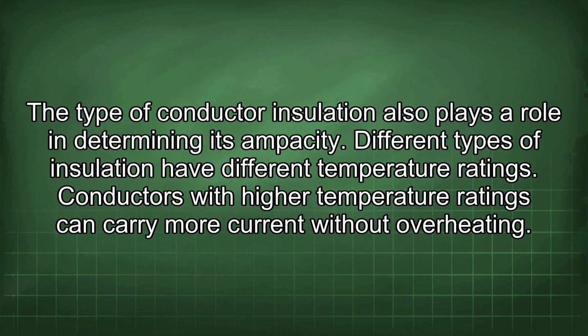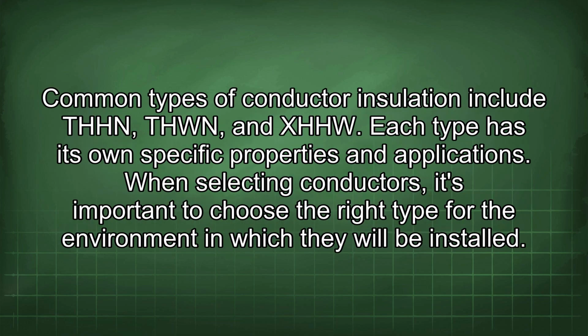The type of conductor insulation also plays a role in determining its ampacity. Different types of insulation have different temperature ratings. Conductors with higher temperature ratings can carry more current without overheating. Common types of conductor insulation include THHN, THWN, and XHHW. Each type has its own specific properties and applications. When selecting conductors, it's important to choose the right type for the environment in which they will be installed.